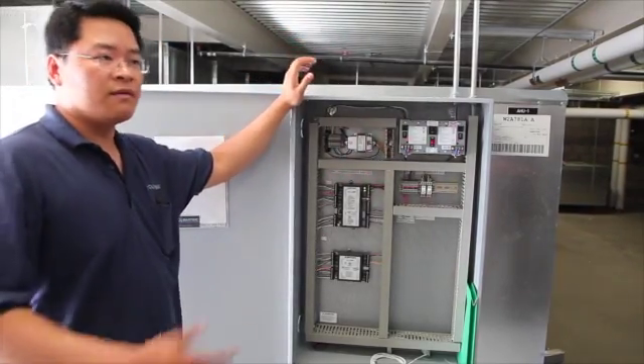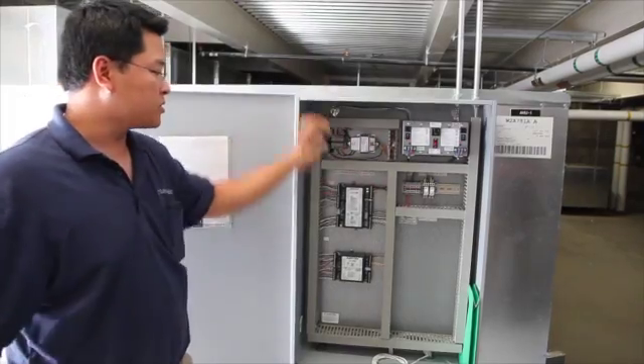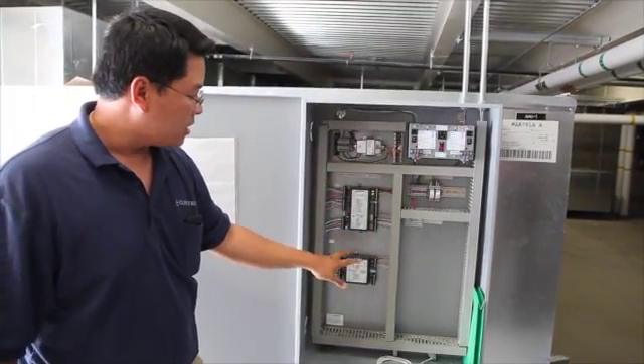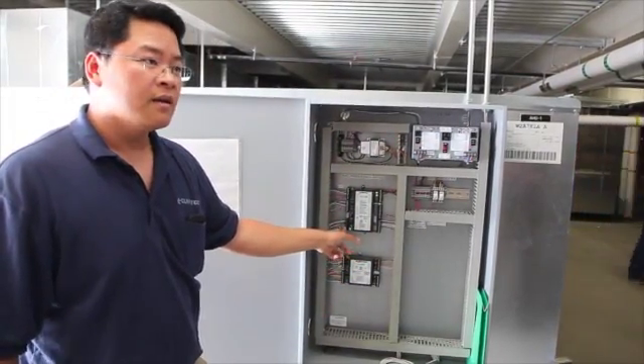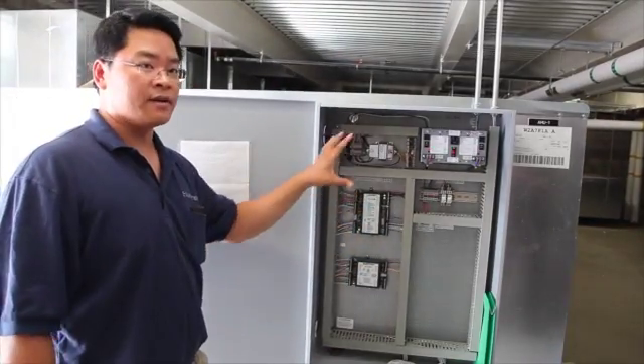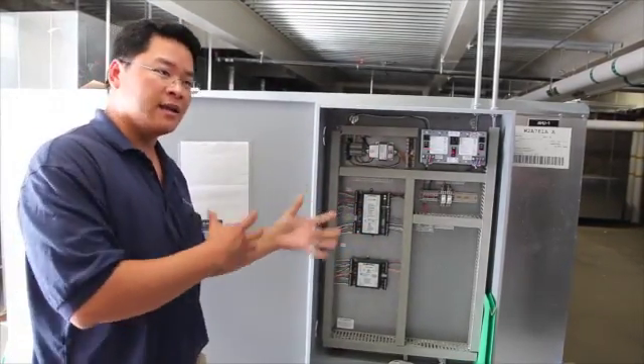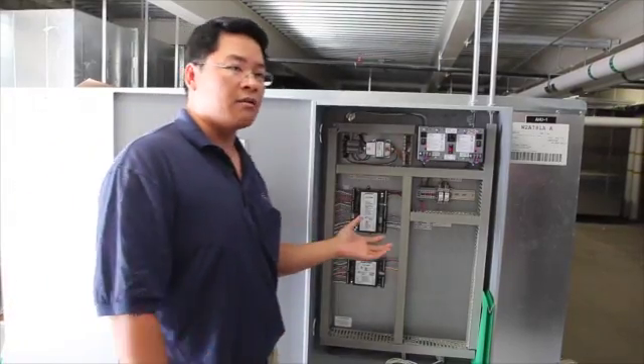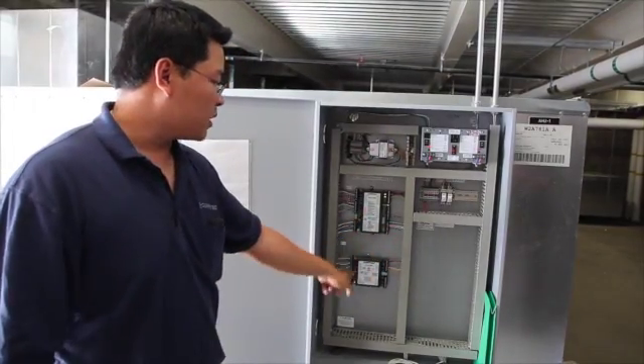Everything that he mentioned in terms of valves, damper positions, it's being controlled by these types of controllers. They have a light indicator here. The first thing you want to do when you have an issue with this unit on your front end, that you're not seeing values or units not running, you want to make sure you look at that blinking light.